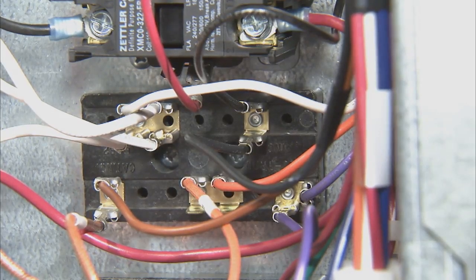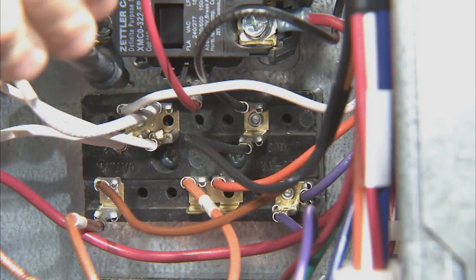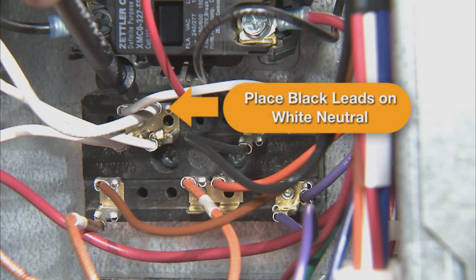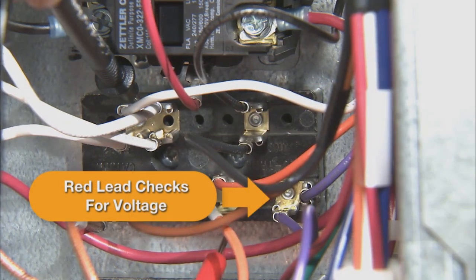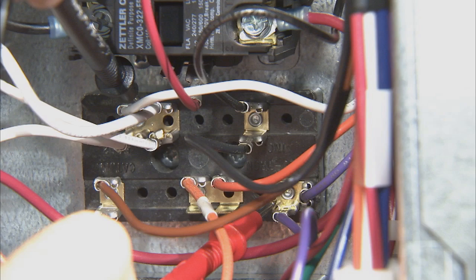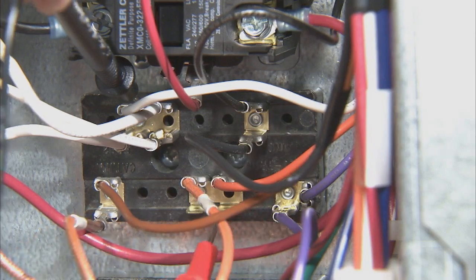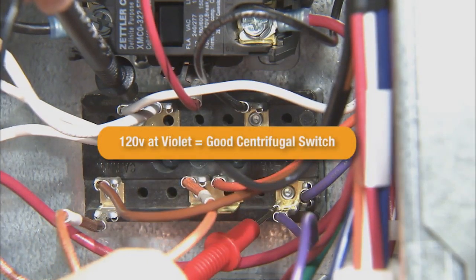The white wires on the upper left of the terminal block are the neutral. The black testing lead of the voltmeter will be placed on the white neutral. The red lead will be used to test for voltage. Voltage will be checked at each point in the circuit to find where the voltage stops, which will identify the issue. First, place the red lead on the violet wires.